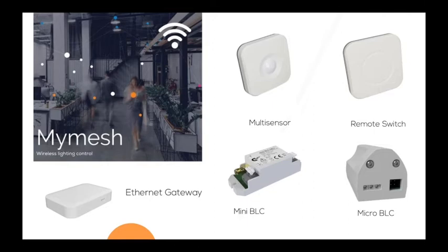At the bottom left there's also a plug-in for an aerial - an external aerial if you've got an all-metal luminaire, to mount the head outside the unit or through the cable gland. For example, if you've got a linear suspended metal luminaire, you've got 4 sides of metal and it's sometimes hard to get a signal out. Mount this near the cable gland, pull the little external antenna out, and you're going to get a considerably better signal with no issues.